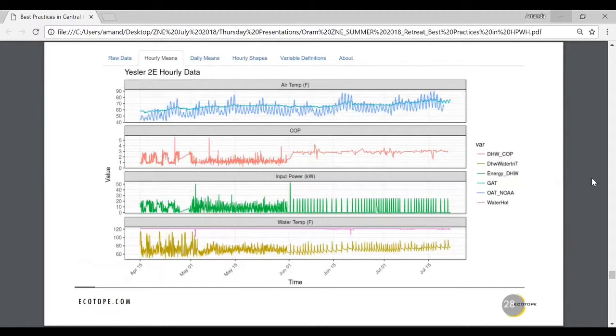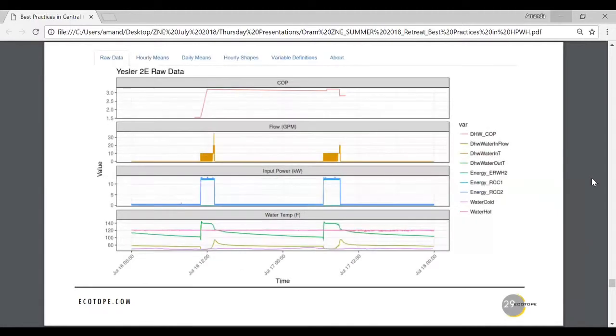One thing I'll point out in the water temp graph down at the bottom, this is the entering water into the heat pumps. If you look at the COP above, you can see we've kept this entering water below about 80 with the new control setup we've got going. That directly correlates to COP, so that's a huge piece there. It's just making sure your entering water into your heat pump is always below 90 as a good target, and then you get that with single pass design.